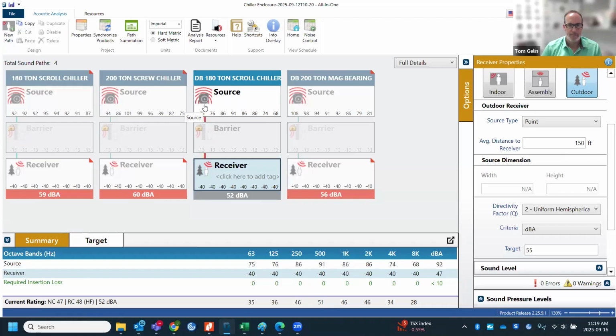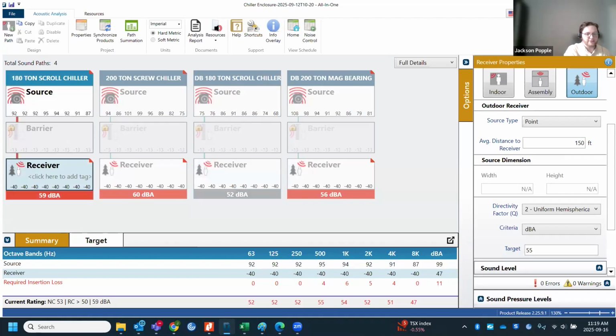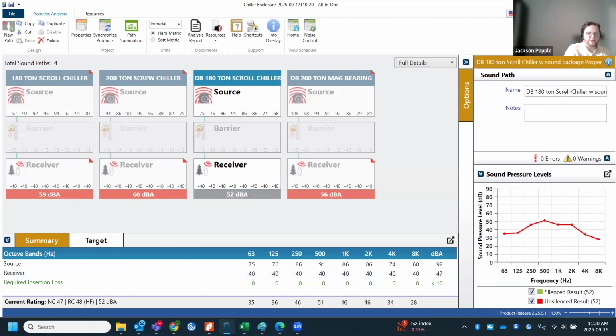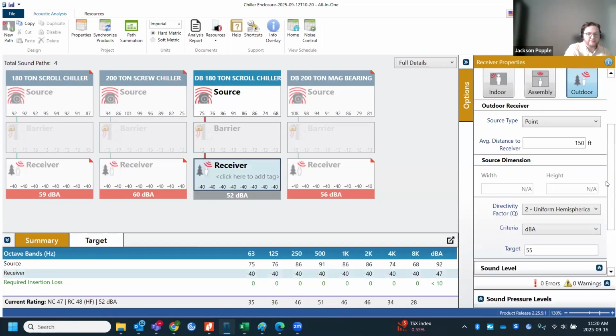Once we have that all changed over, we have raw sound power in dB here. We can look into our receiver and see a lot of these are right around where we want to be. They're all a little bit higher, except for the scroll chiller with the sound package, than the 55 dBA we're looking at. But even with this, if we look at the receiver, this receiver is under pretty ideal conditions. It's going to be 150 feet away, which is probably what we'll see, but it might be further.